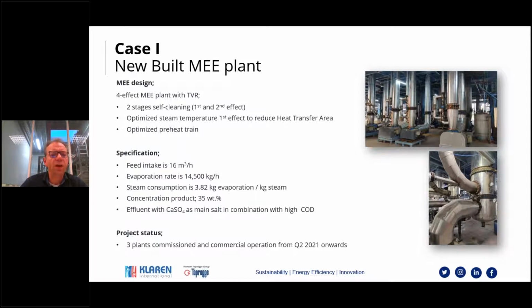To give you an idea about the specification of the plant, we were talking about a feed intake of 16 cubic meters per hour. But what is really more important is the evaporation rate. That is around 14,500 kg per hour. So you can see that's almost 90% of the incoming feed. Of course, if your inlet concentration is higher with the same outlet concentration, you can also take in more feed. But the core is really the evaporation rate that is promised. The steam consumption is around 3.8 kg of evaporation per kg of steam, which is quite normal for this type of plant. And the final concentration that we reach is around 35%, where we already have some solid formation, but not that much, because in this case the effluent is sent to a spray drying plant, which will at the end make for the conversion to ZLD.